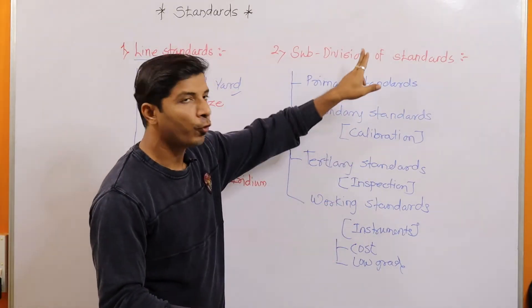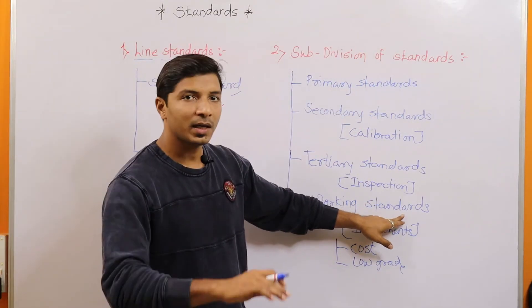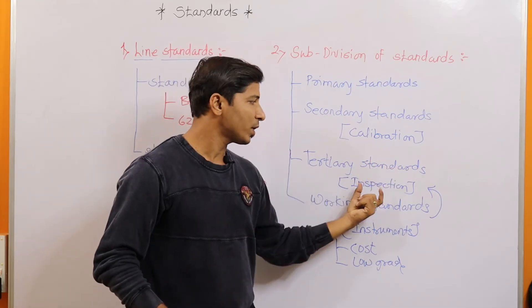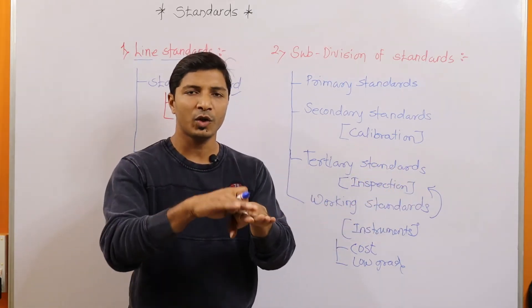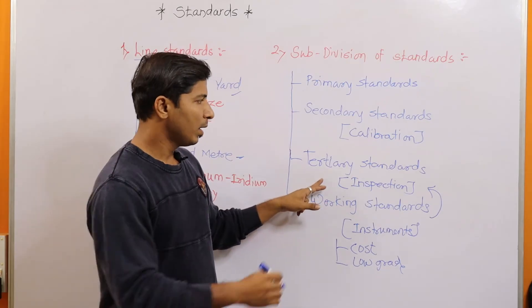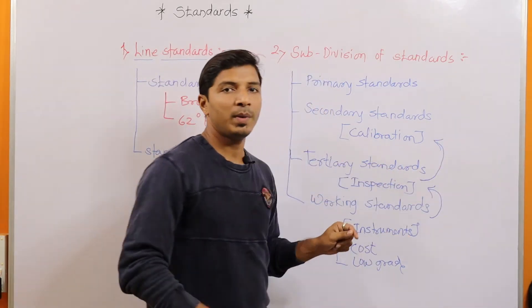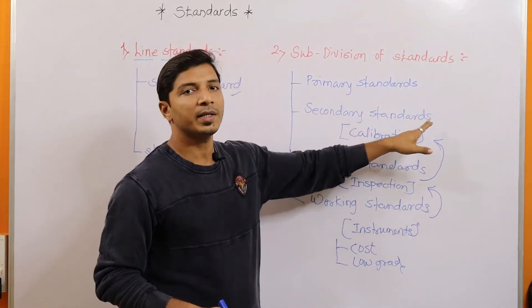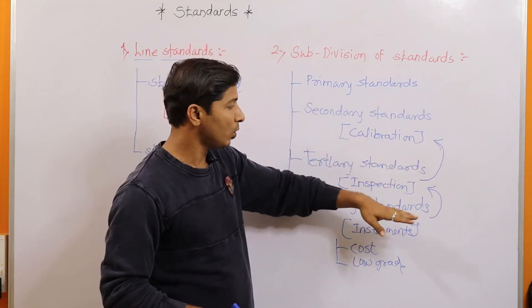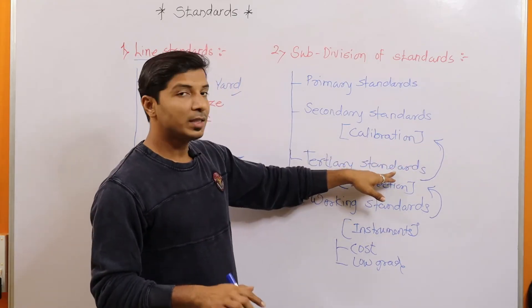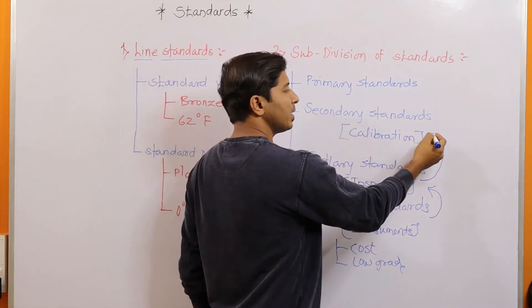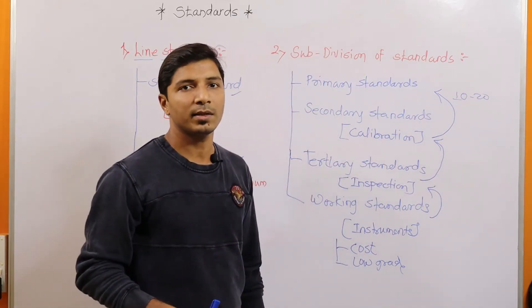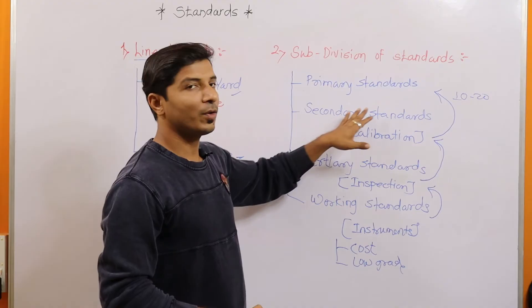Now you can identify the flow. When working standards are frequently used, they need to be inspected with the help of tertiary or inspection standards at frequent intervals — maybe after a week or two weeks. But at specific intervals, maybe after one or two years, the tertiary standards need to be compared with secondary standards to see whether the accuracy level is maintained. Then secondary standards are again compared after 10 to 20 years with primary standards to ensure the accuracy of the secondary standards.